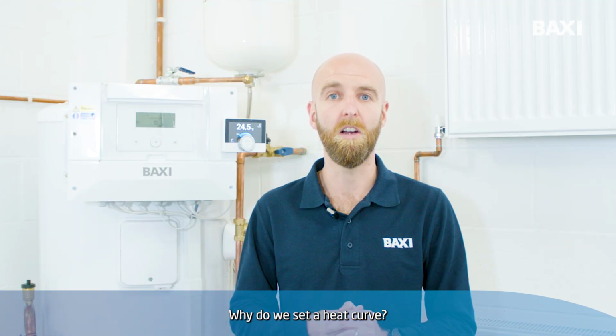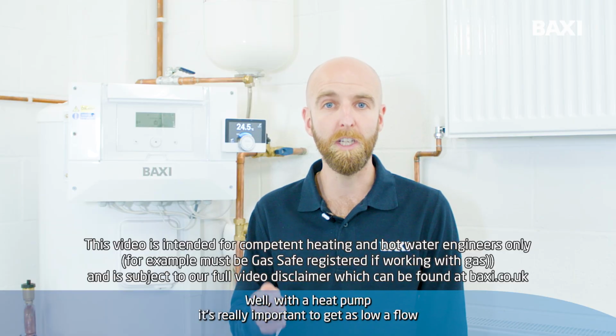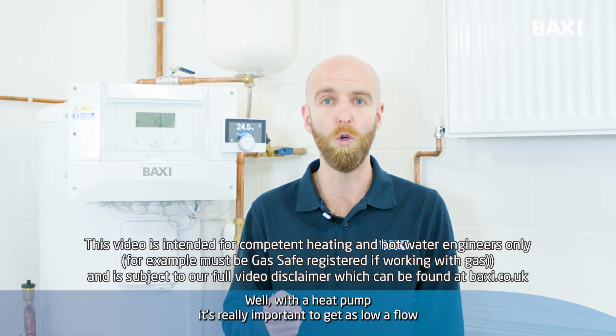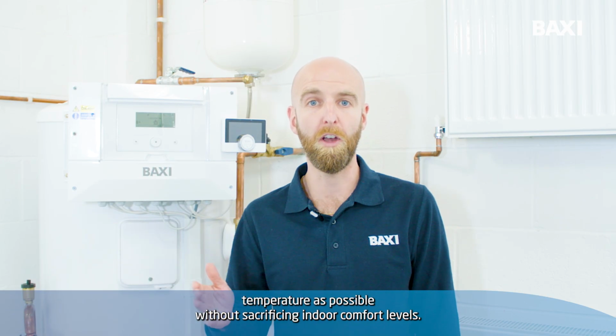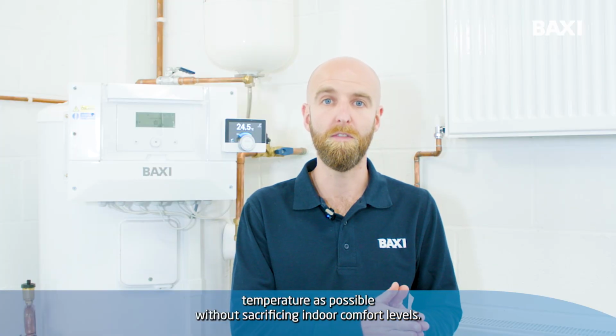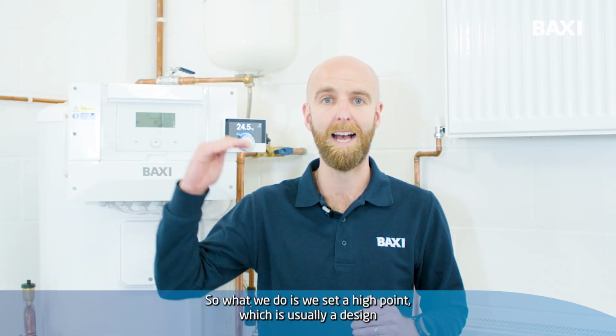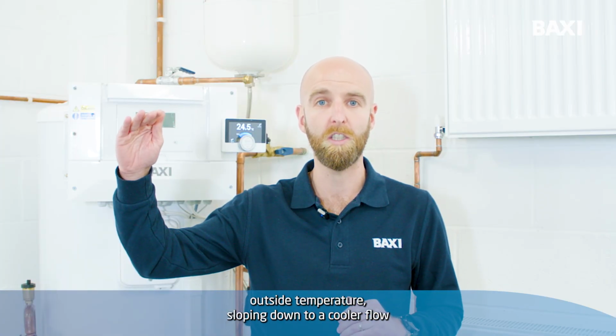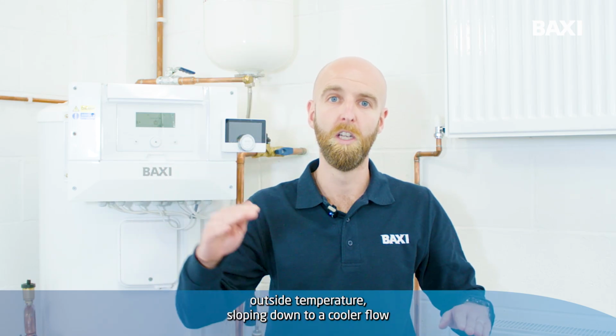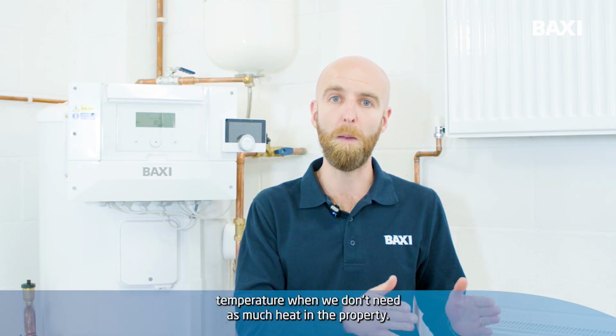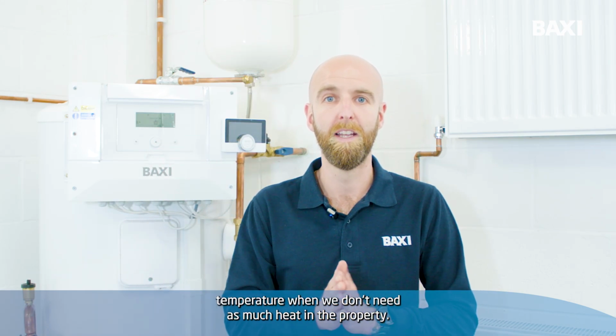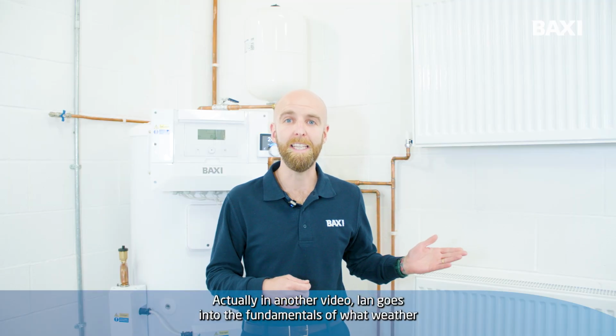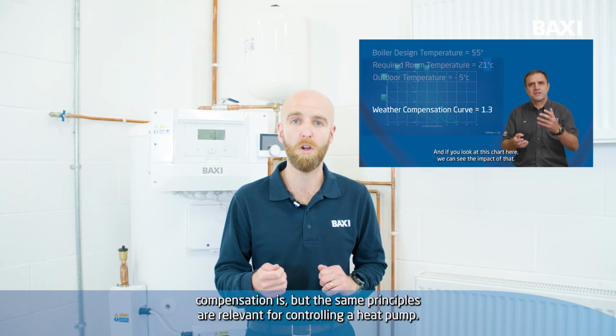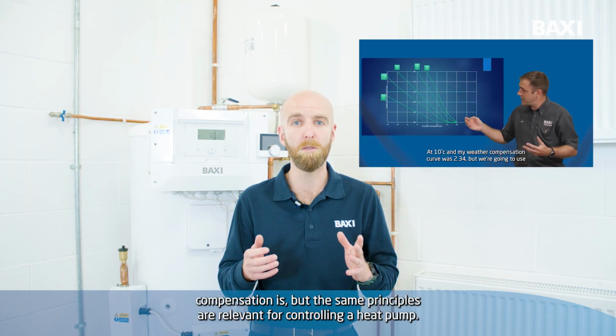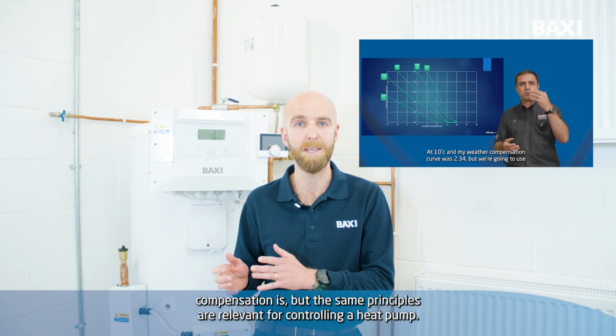Why do we set a heat curve? Well, with a heat pump, it's really important to get as low a flow temperature as possible without sacrificing indoor comfort levels. So what we do is we set a high point, which is usually our design outside temperature, sloping down to a cooler flow temperature when we don't need as much heat in the property. Actually, in another video, Ian goes into the fundamentals of what weather compensation is, but the same principles are relevant for controlling a heat pump.